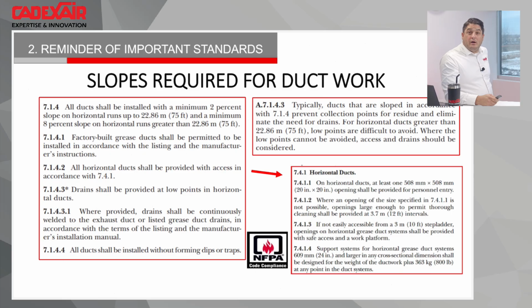And maybe one other point: if the access door is not easily accessible from a 10-foot top step ladder, we're supposed to have a safe workplace to work. Because our guys go to a lot of difficult places, and I will say we have probably two guys that should work at Cirque du Soleil, how they can handle everything, but it's not the way we should work to work safely. So you need to have a little bit of thought about the guy that will clean the ductwork. And if you think there's a magical robot that will go through the ductwork and take out the grease, no, you put degreaser, you scrape it, power wash it.